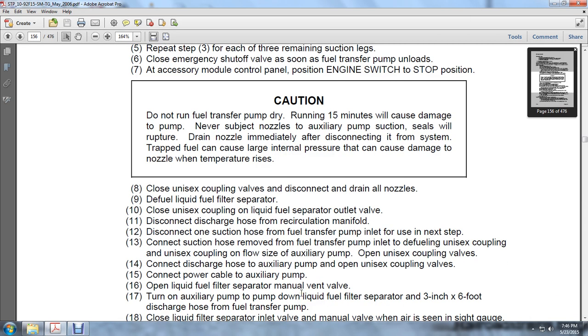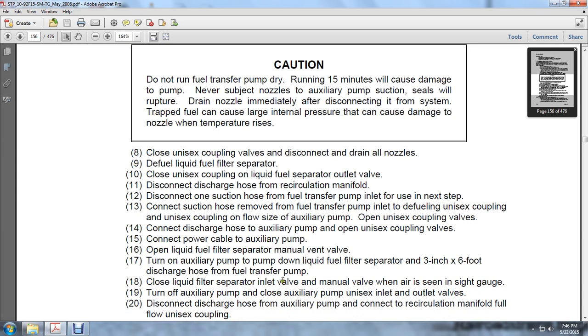Open the liquid fuel filter separator manual valve. Turn on the auxiliary pump to pump down the liquid fuel filter separator and the 3-inch by 6-foot discharge hose for the fuel transfer pump. Close the liquid fuel filter separator inlet manual valve when air is seen in the sight glass. Turn off the auxiliary pump and close the auxiliary pump unisex inlet and outlet valves.